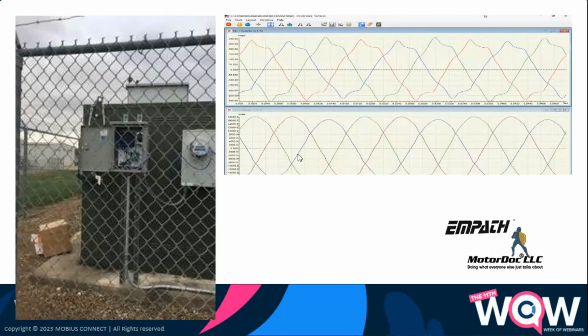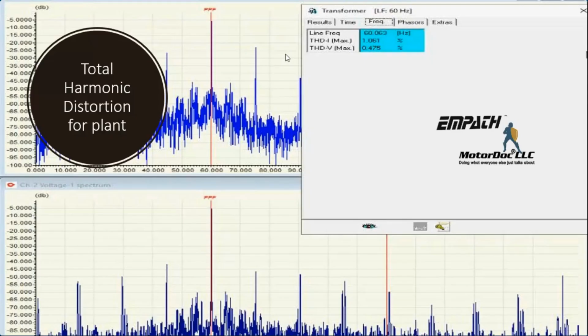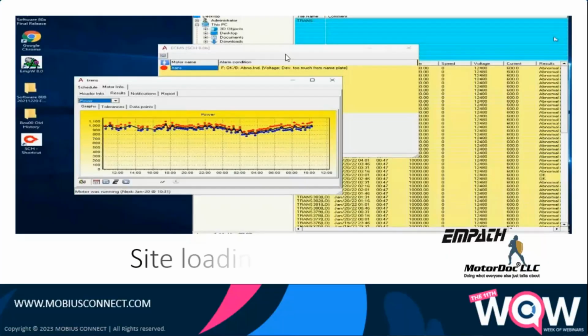This is that plant. We were doing measuring at the utility meter. We just now concluded that project. This is not unusual. As a matter of fact, most of the waveforms we're looking at right now don't even look this pretty. They look much, much uglier. We're putting a lot of stuff on the grid that we had not been placing there before. So yeah, the harmonics are generally pretty high. If we address those harmonics, we'll get past that.